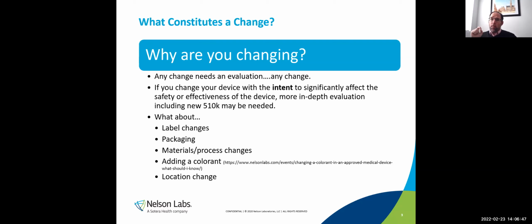So the second bullet point there is important. It says, if you change your device with the intent to significantly affect the safety or effectiveness of the device, more in-depth evaluation, including a new 510K, may be needed. That's directly from the FDA. So lots of times we make changes to a device that we assess, but that doesn't necessarily mean it needs to go through a new 510K. There needs to be some kind of safety assessment internally to evaluate that impact.